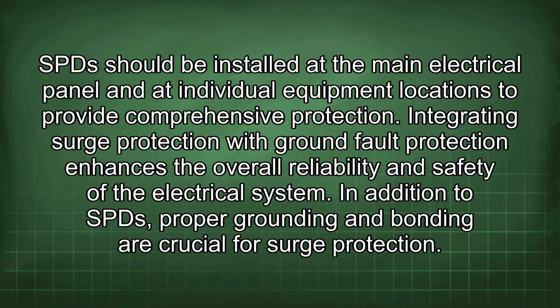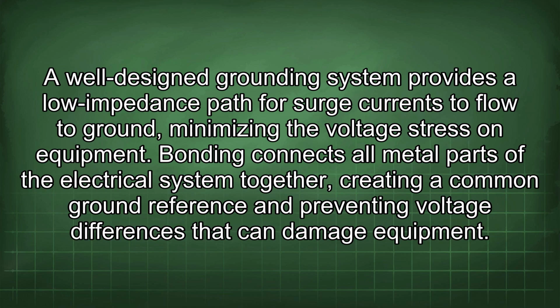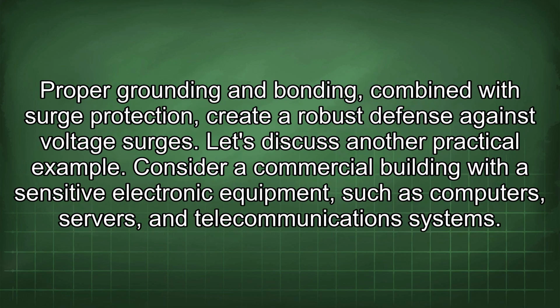In addition to SPDs, proper grounding and bonding are crucial for surge protection. A well-designed grounding system provides a low-impedance path for surge currents to flow to ground, minimizing the voltage stress on equipment. Bonding connects all metal parts of the electrical system together, creating a common ground reference and preventing voltage differences that can damage equipment. Proper grounding and bonding, combined with surge protection, create a robust defense against voltage surges.